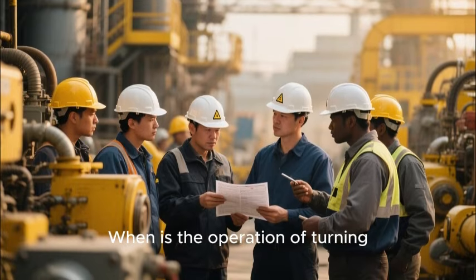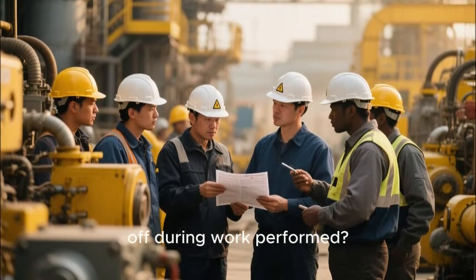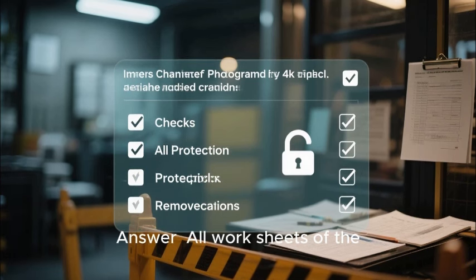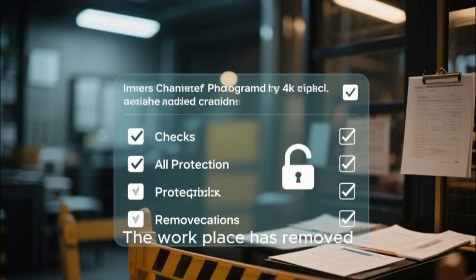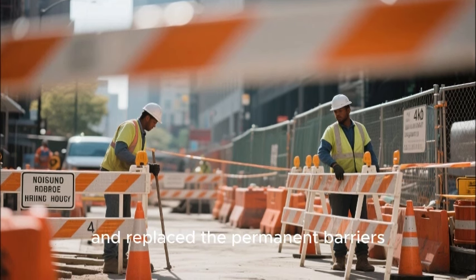When is the operation of turning on power to the equipment that has been cut off during work performed? Answer: when all worksheets of the related work units have been locked to ensure that the equipment will be energized absolutely safely, the workplace has removed signs and temporary barriers during work, if any, and replaced the permanent barriers.